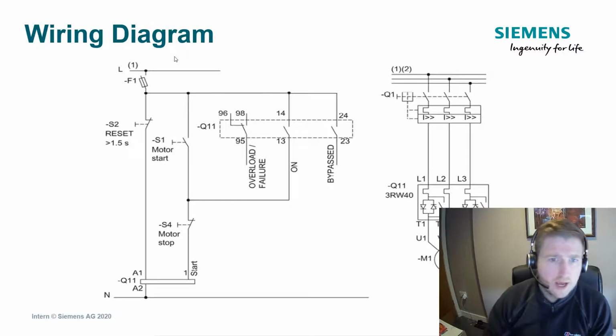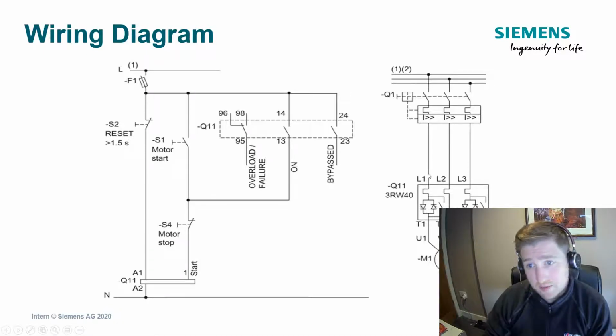Now on the 3RW30 you don't have options for signaling for an overload failure, and you also don't have a signal to say that the device has gone through the bypass mode. So with the soft starters, the way that they work is when this device is switched on, the power and the voltage runs through these power semiconductors here, and they continue to do so until you've reached the time that you've allocated on the potentiometer for the ramp up. And if the device has reached the full operational voltage by that time, these thyristors will then be switched out by this mechanical bypass, which is what this contact is actually signaling.